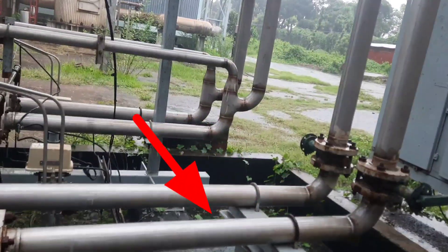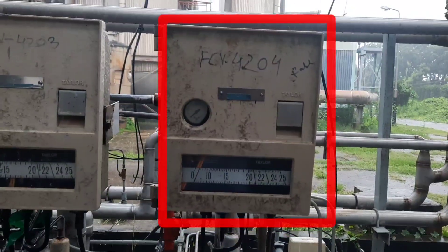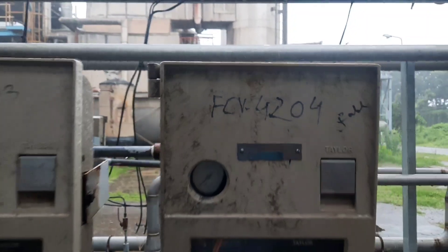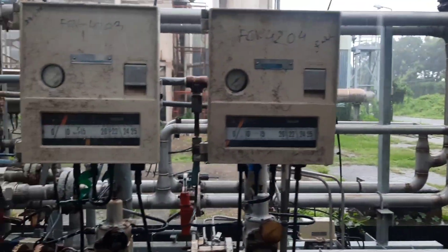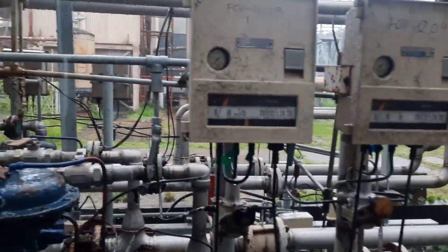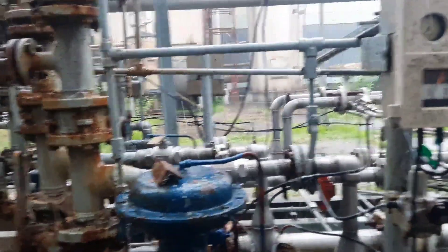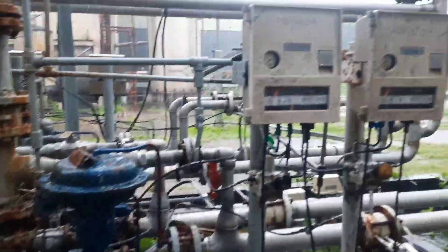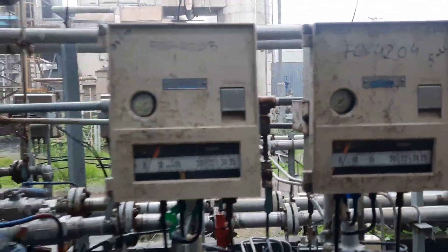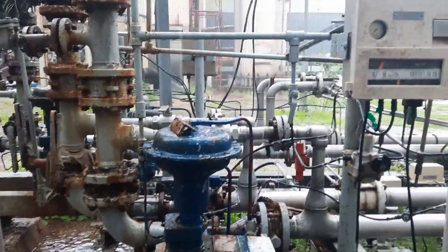There is one manual valve which we will open. After opening this manual valve, in our plant there is one flow controller valve FCV-4204 — this is the air controller. By this controller we have to maintain the flow. During backwash, we maintain 52.5 cubic meters per hour flow. Normally, in our plant backwash time is 15 minutes, though different plants may have 10, 15, or 20 minutes. We are providing this water flow of 52.5 cubic meters per hour for 15 minutes.